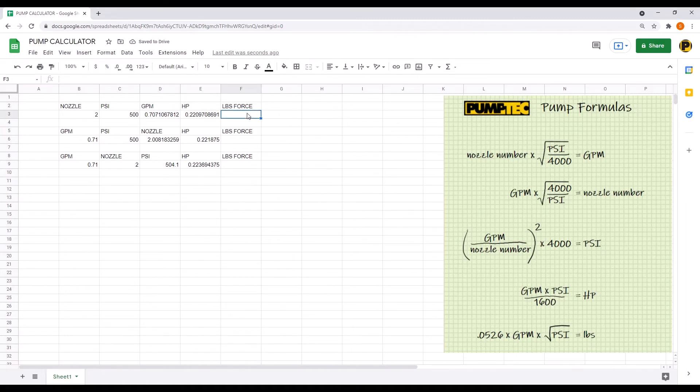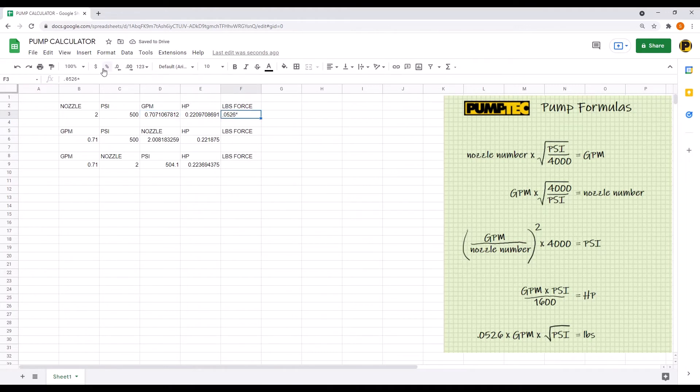And now type in the formula, it's the last formula for pounds equals .0526 times GPM times the square root of PSI.